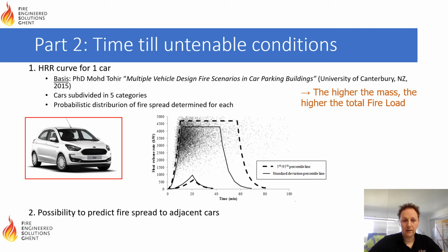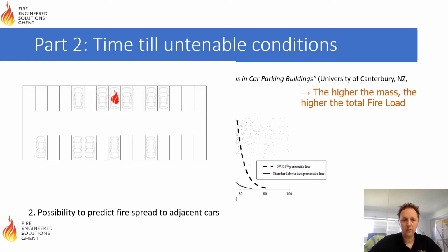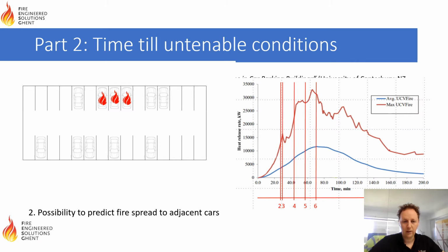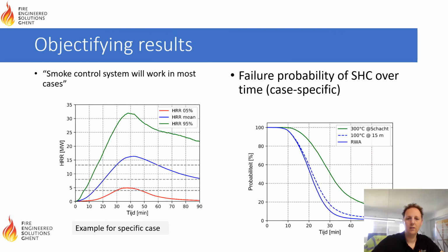The second part is the possibility to predict the fire spread to adjacent cars. Basically a simple radiation model that will determine, based on the distance to the adjacent cars, how quickly the fire could spread to second, third, etc. number of cars. The interesting thing about this approach is that we're able to objectify the results. Instead of saying we assume that the fire brigade will arrive at 15 minutes, and we assume that the design fire is not higher than 8 megawatts, what you're able to do here is say, depending on the time of arrival of the fire brigade, we're going to look at what's the distribution of the heat release rate.